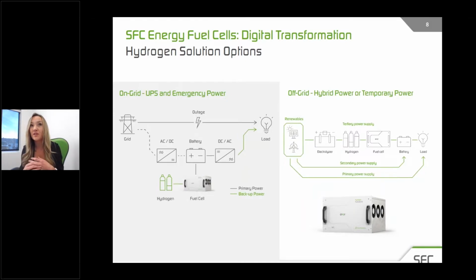Let's say we've got a client with a critical grid-supplied telecom tower, and instead of using a diesel generator, they want to explore a fuel cell option. Similar to the methanol fuel cells, it's just going to wait for that UPS, and it's only going to turn on in the event of an emergency when the grid goes down. So you have a battery bank, and the fuel cell turns on based on the battery bank, taking less than a minute to produce full power. Once the grid is back up, the fuel cell sits dormant, with no degradation while in standby mode — it's just waiting for the need to back up the grid.